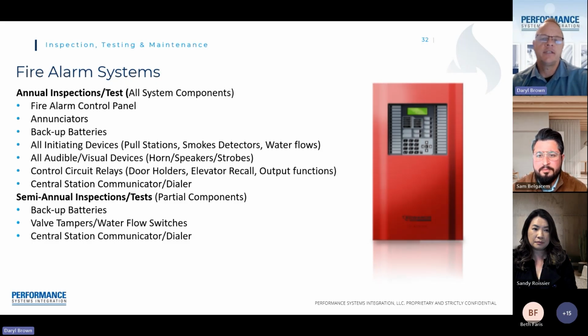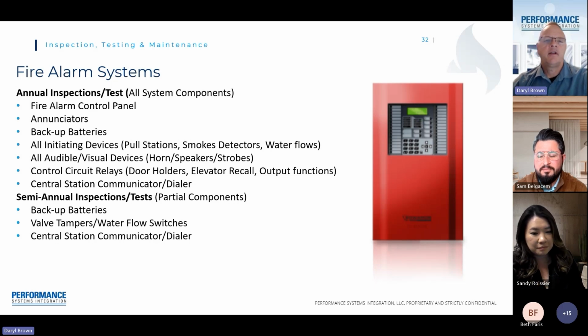So when we're doing visual and operational tests, say doing water flows on a sprinkler system, we're also verifying that that water flow activates the alarm system. Thereby, we're satisfying the NFPA 25 code as part of a sprinkler inspection, but we're also satisfying the NFPA 72 code as part of fire alarm. You need to be licensed by the state of California to do both. So if a contractor's doing your fire sprinkler inspections and they're doing the water flow and the valve tampers as part of their sprinkler test, it doesn't satisfy your fire alarm test unless they're licensed in both.